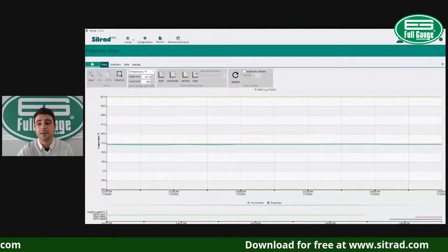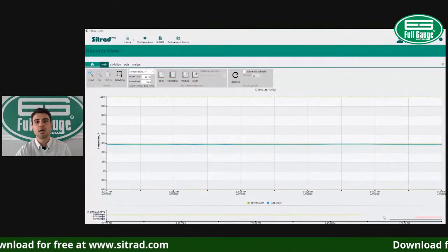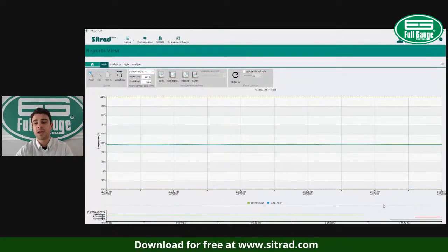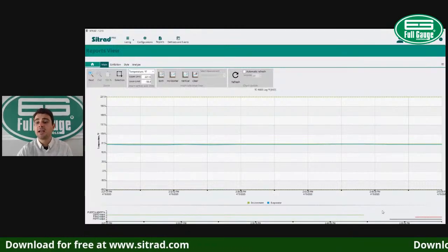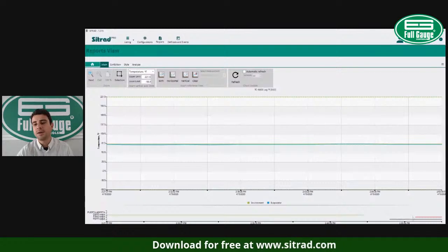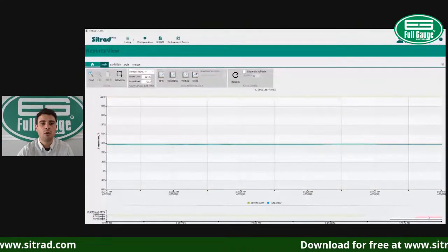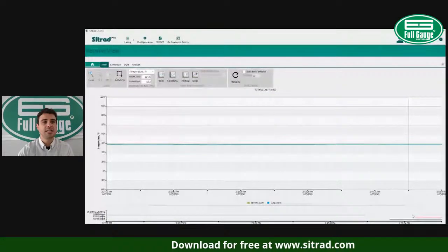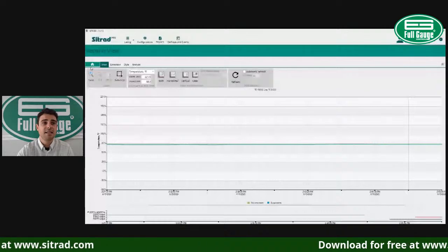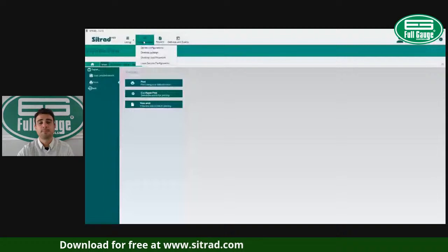That's the draining time. That's the time we let the system drain, so that water that came from the defrost cycle doesn't freeze up and ice up the coil again. And then the fan delay cycle, when the fan was off and the compressor was on. And after the fan delay, we have our normal operation with the compressor on and the fan on. So by taking those reports, you can easily analyze the system data and easily identify potential improvements.